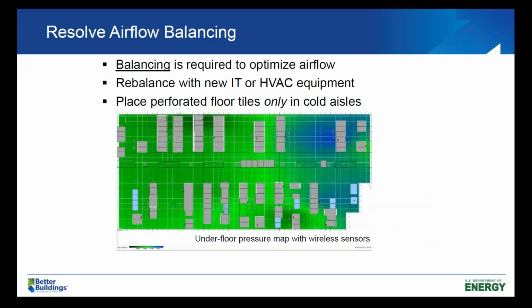Okay, so balancing is necessary to get the optimum airflow. Whenever significant changes are made in the data center, it should be checked and balanced as necessary. One of the very early steps of this process is to make sure that there are no perforated tiles except in the cold aisles. Next slide.